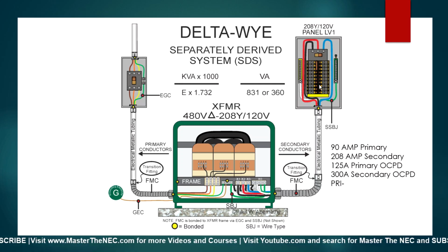Now over here, we calculated previously at 208 for our secondary, and we did 125%. That was 260. It didn't correspond to a breaker, so we were able to go up to 300. If this was a 300, these conductors have to be rated for 300, because we can't use the next size up rule on secondary conductors. So these are rated at 300 amps.